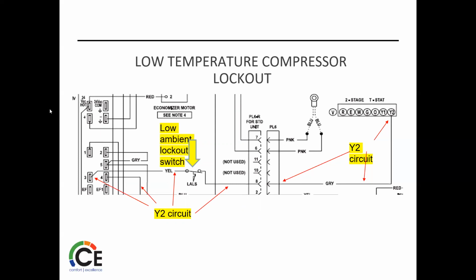So here's your low temperature compressor lockout, because the low temperature switch is either closed or open and says, hey, we're not going to do it that way. We're just going to pull in some outside air. If the outdoor airstream, which is used to lock out the compressor, is below 42 degrees, special accessories are needed for equipment operation below that. So now we're talking low ambient kits and whatnot.